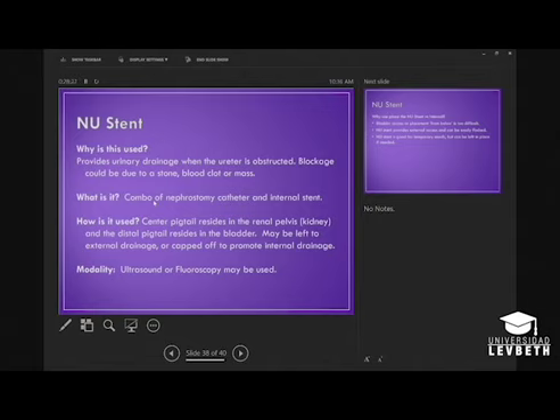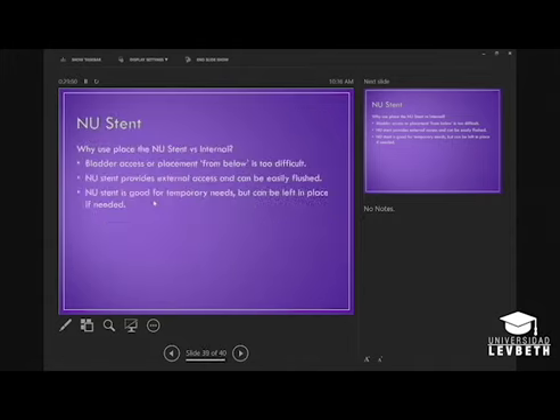Same sizes as Cook, same size as Boston, 8 or 10 French, and they come in 22, 24, 26, or 28 centimeters. The difference between the lengths is the distance between the two pigtails. So everybody's anatomy is different. Some may have a longer ureteral tract, so they need a 28 centimeter pigtail catheter, versus someone with smaller anatomy who may just need a 22. This is just why you would use it. It's good for temporary relief, but a lot of times the patient may need surgery.